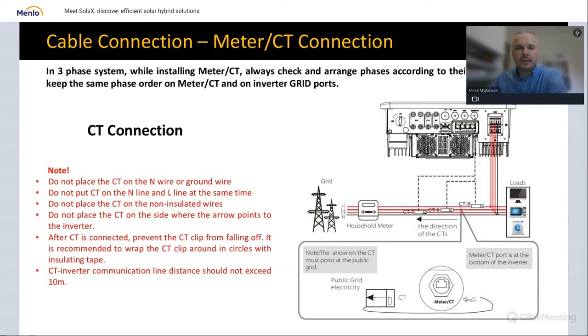Meter and CT connection. It's very important to match the correct pins when crimping the RJ45 plug. You have to connect with correct pins, because the meter is using only pins 4 and 5, and the rest of the pins are used accordingly by the CTs.